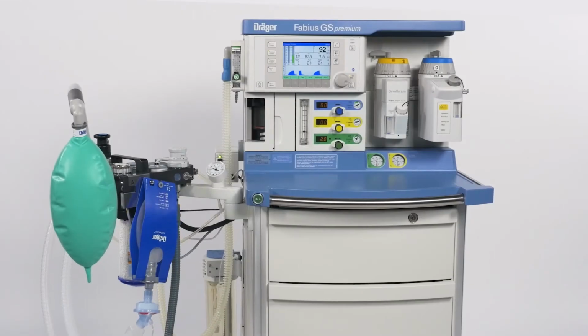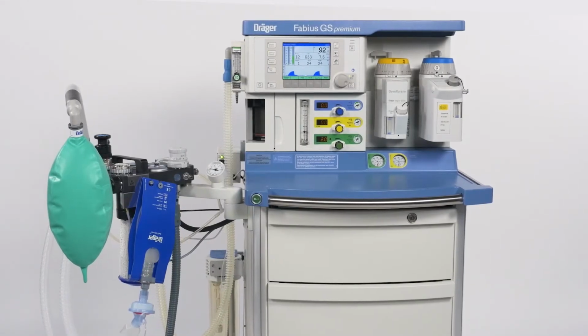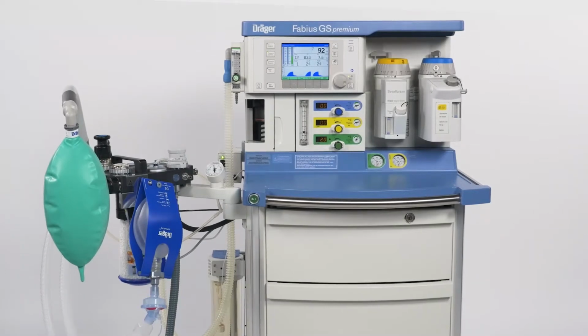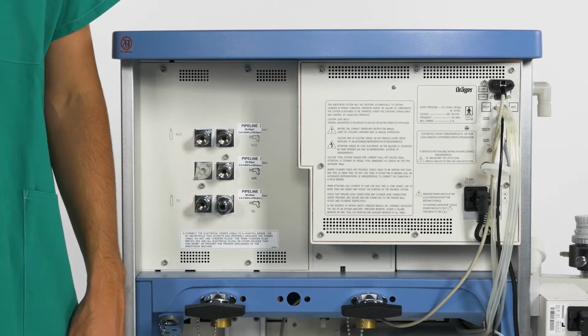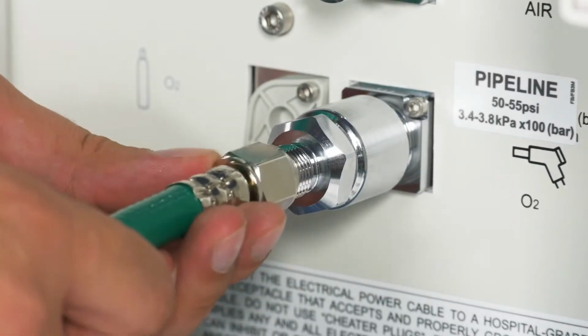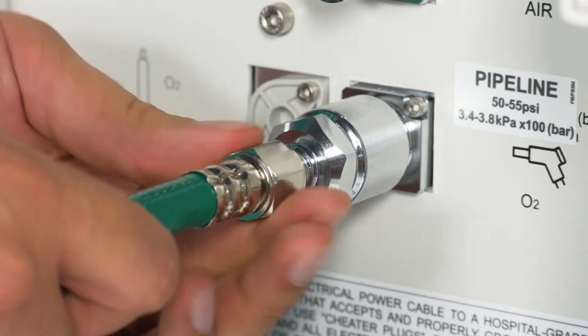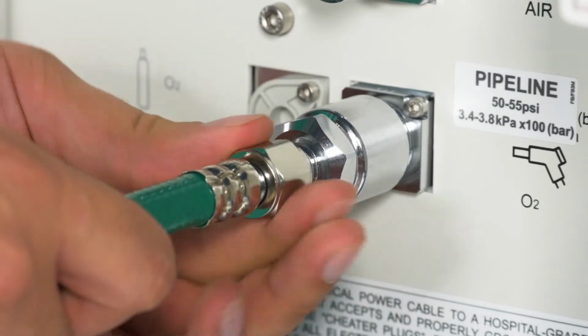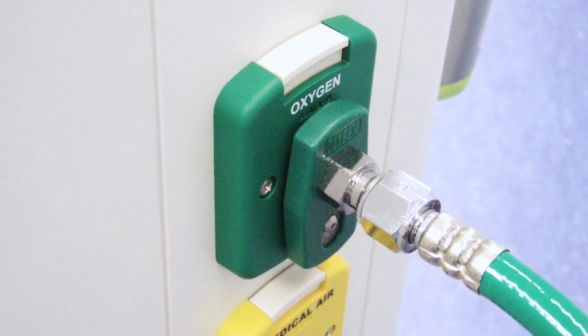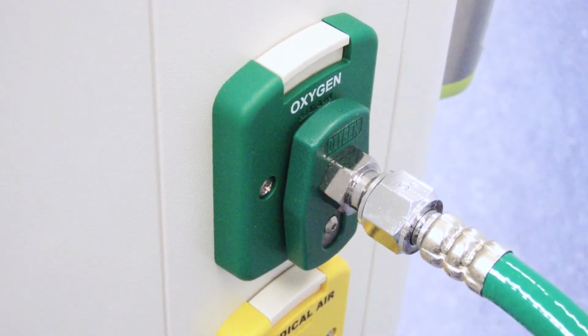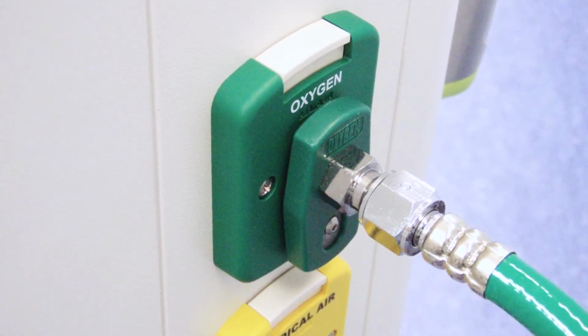In this part, we would like to show you how to set up the Fabius GS Premium. First, we check the central gas supply connections. Connect the central gas supply hoses for oxygen, medical air and nitrous oxide to the outlets on the rear side of the anesthesia machine. Connect the central gas supply hoses to the relevant outlets in the wall.